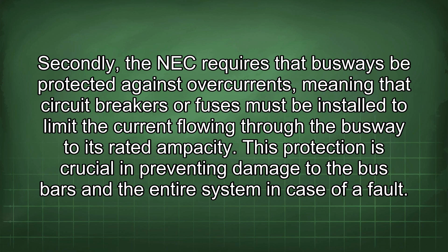Secondly, the NEC requires that busways be protected against overcurrents, meaning that circuit breakers or fuses must be installed to limit the current flowing through the busway to its rated ampacity. This protection is crucial in preventing damage to the bus bars and the entire system in case of a fault.